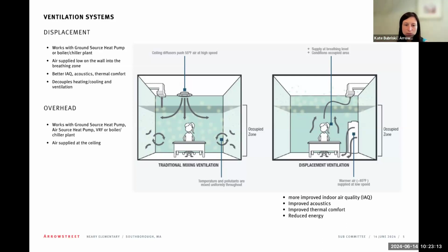Lots of times we've had people who walk through the building and say, I don't even know if this is on, but it's on. You don't hear that whoosh of air. And then it provides more thermal comfort. Because of that, you're not getting drafts from that system like you might have in an overhead system, and reduced energy. So that system is more efficient from the ventilation system in terms of how it's supplied.